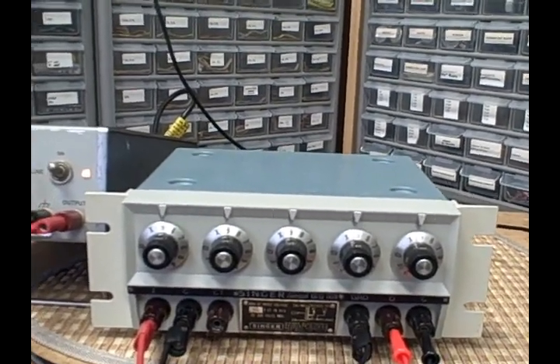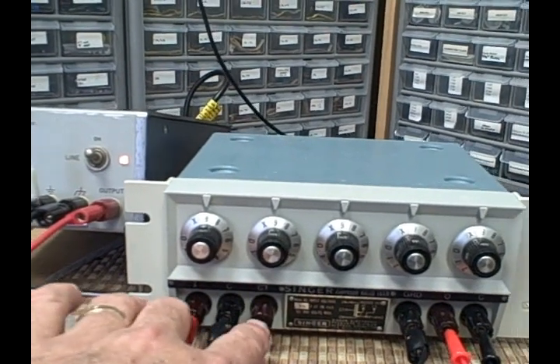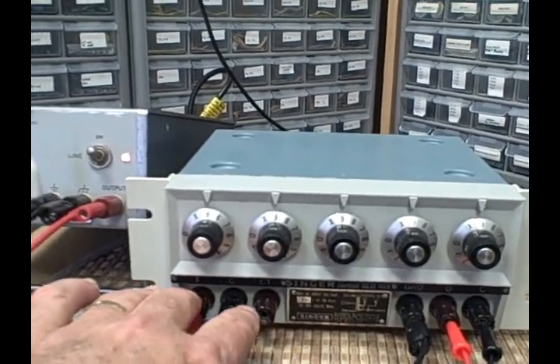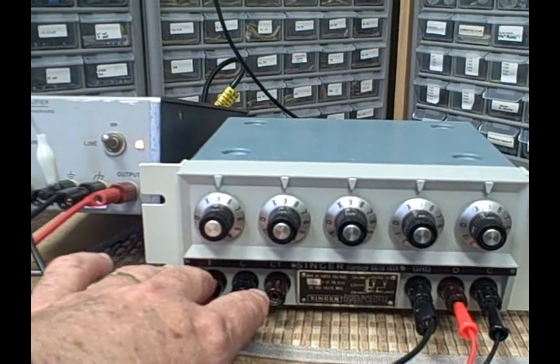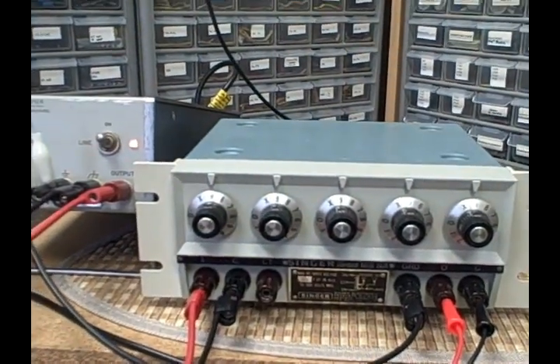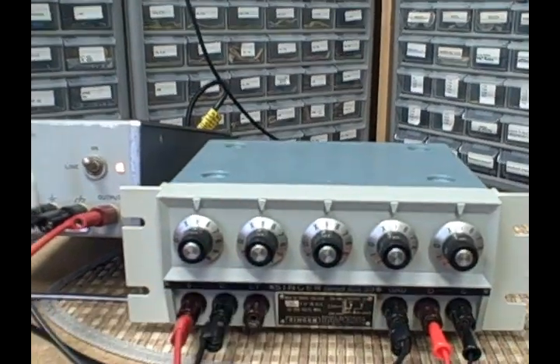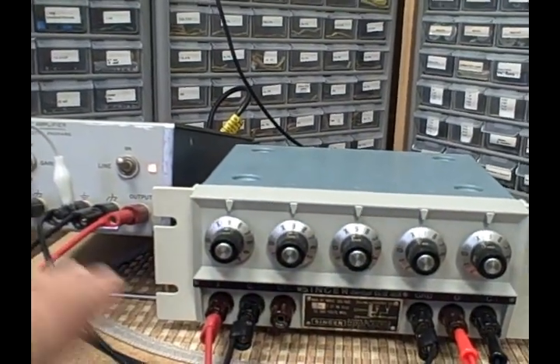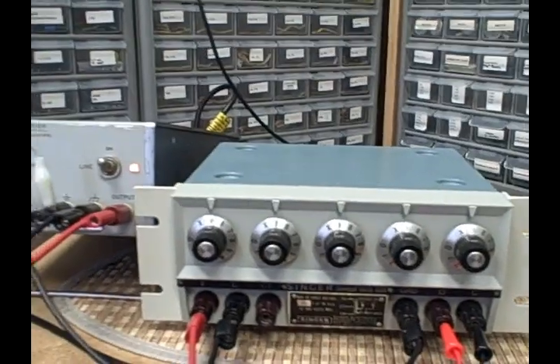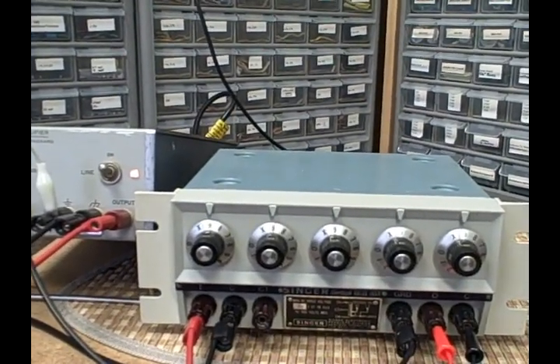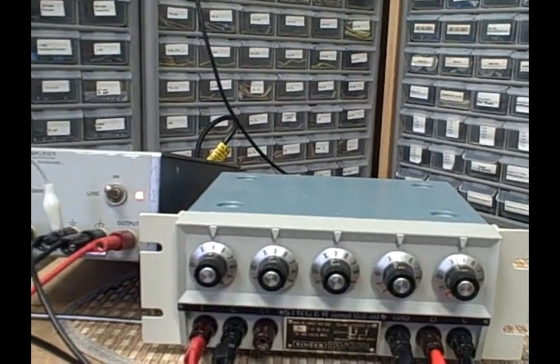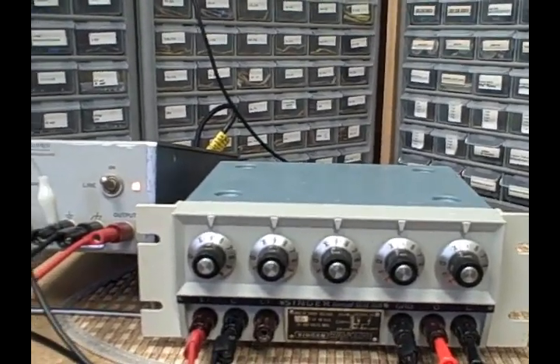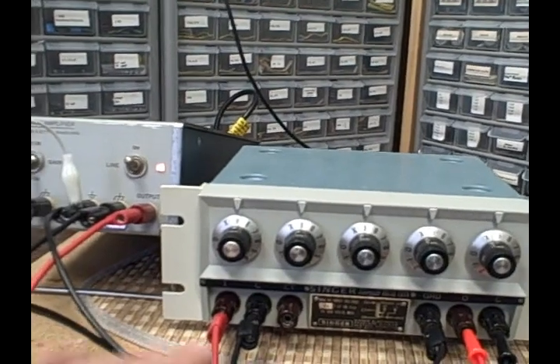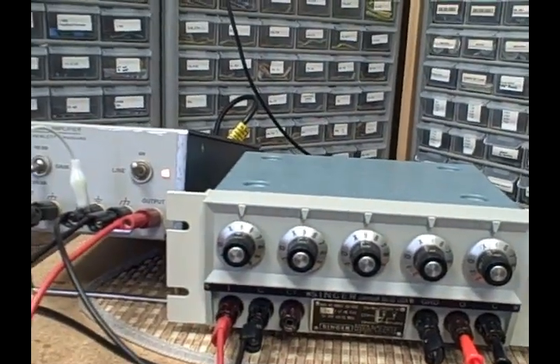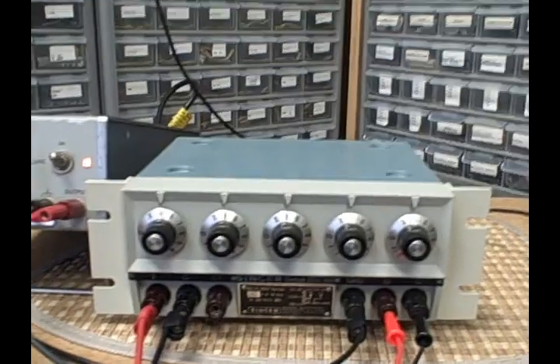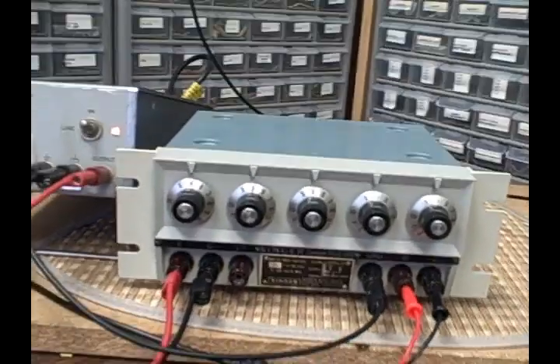And this particular unit also has two inputs. I've got an I input, I think it says, and the other says a center tap or CT input. If I was to go into the center tap, I'm taking the voltage that I'm bringing in and I'm doubling it. So I put a 5 volt in, I get a 10 volt signal through the ratio transformer. I believe it is at a slightly reduced precision doing that, so I'm running into the I terminal. All right, let's carry on.